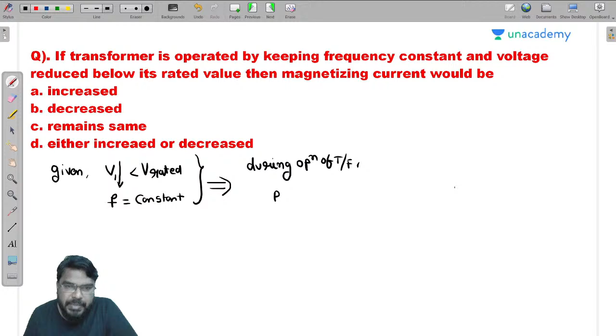Here, the applied voltage V1 is less than its rated value, and the frequency of the transformer is constant, equal to its rated value. So during operation of the transformer, what is the condition? B maximum is directly proportional to the V1 by F ratio.